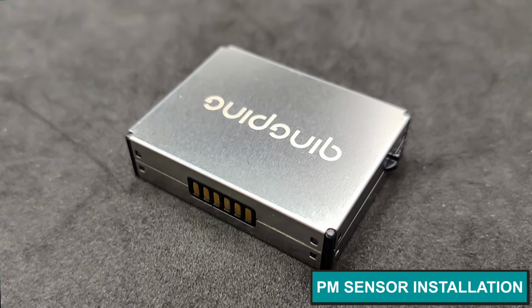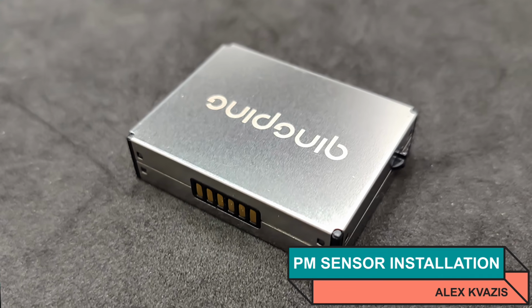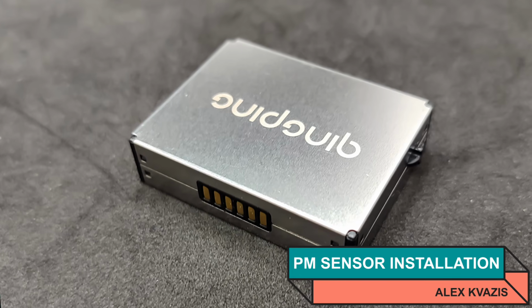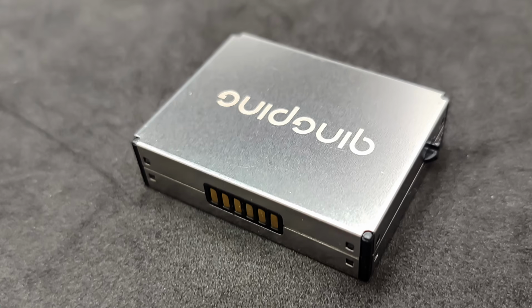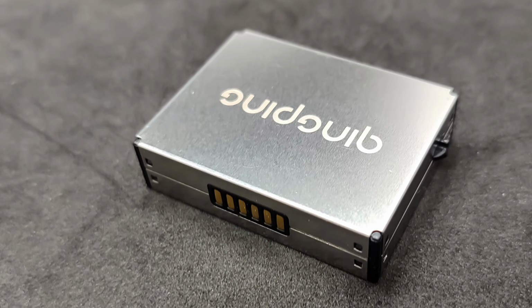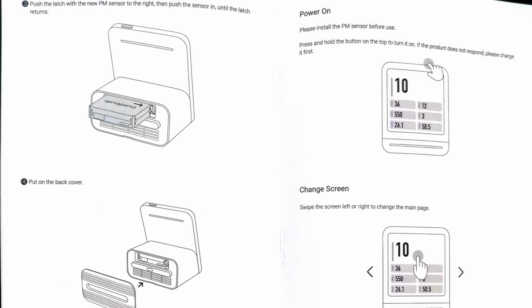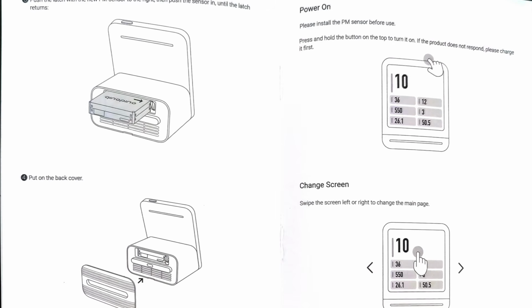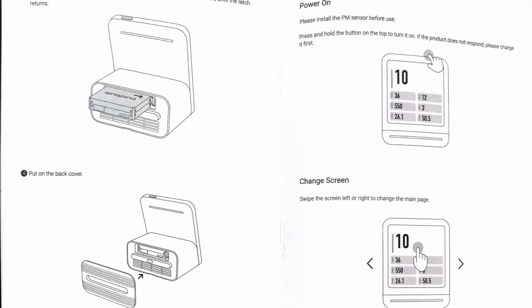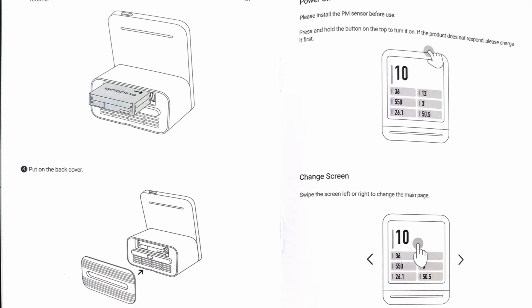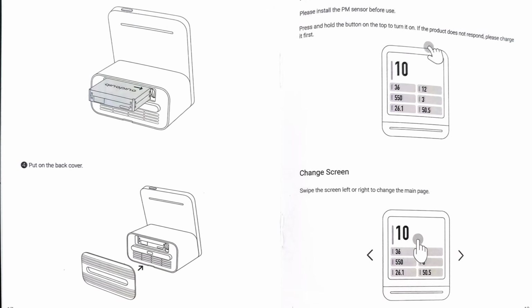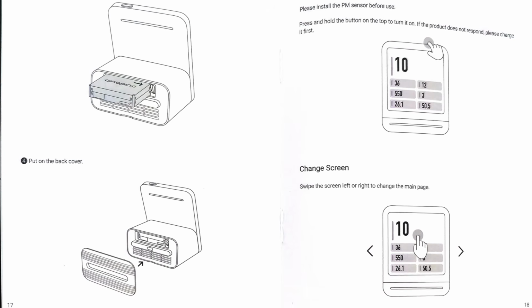This is what the PM sensor itself looks like separately. It is made in the form of a small replaceable module with a contact group on the side. That is, the idea here is precisely that it is a consumable and serviceable element, and not a part of the device that cannot be reached without disassembly. In the manual, the process is shown literally in a few steps. First, insert the PM sensor into the compartment at the back, then close the cover, and after that the device can already be turned on.